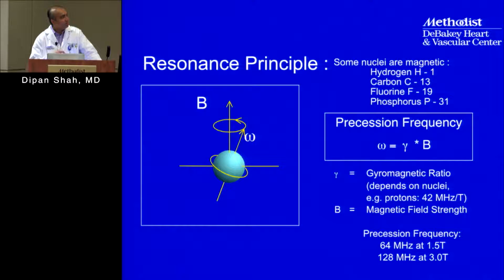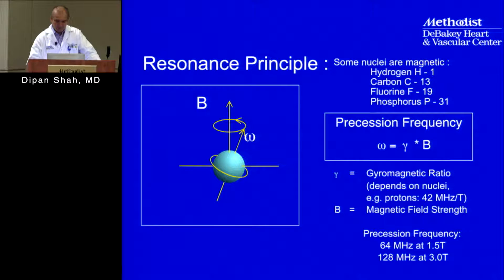At a 1.5 tesla field strength, the hydrogen proton spins at a frequency of 64 megahertz. At 3 tesla, the frequency is 128 megahertz. So protons spin at a frequency directly related to the magnetic field present.